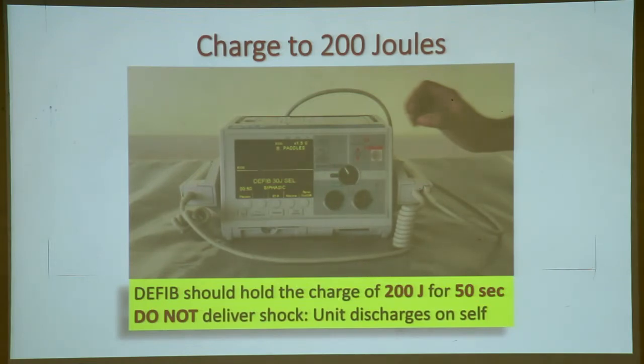And after 50 seconds, if it is able to hold the charge of 200 joules for 50 seconds, then your capacitor is working well. You don't have to discharge it by pressing the buttons. So the last step can be omitted. Second last step, charging to 30. Instead of 30, you charge it to 200 and just leave it. By clock, wait for 50 seconds. If it holds the charge for 50 seconds, your defibrillator is charging well to 200 and it will discharge. You don't have to press the buttons to discharge.